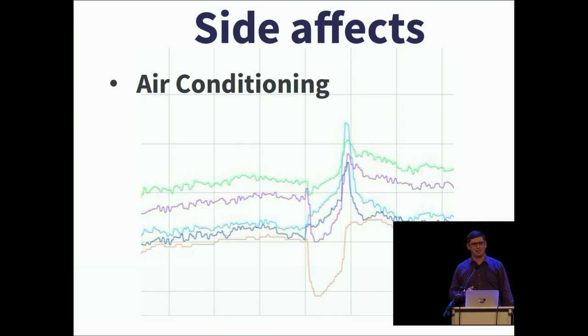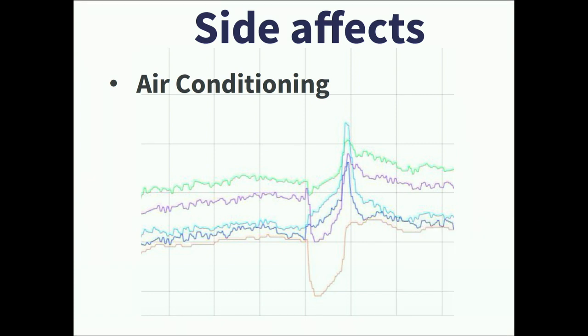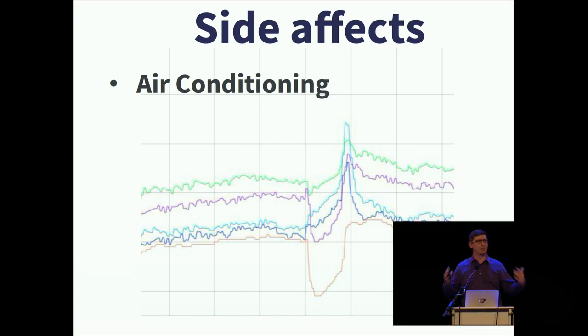Air conditioning has some interesting effects too. For these fire suppression systems to be effective, the room needs a hold time and containment time - you'll hear about integrity tests where you pressurize the room and see how long it can hold that pressure. If you're using a direct adiabatic system with fresh air cooling into the data center, you have to stop doing that for a period. One example someone sent me was an accidental discharge, followed by graphs of their air conditioning showing temperatures creeping up, and having to make a very quick decision: is there a fire in the room, which we technically can't go into? Can we open up all the venting and turn the aircon back on? That's another side effect to be conscious of.